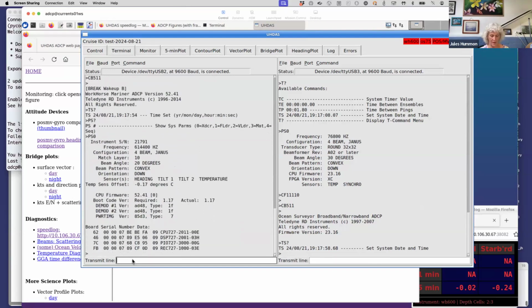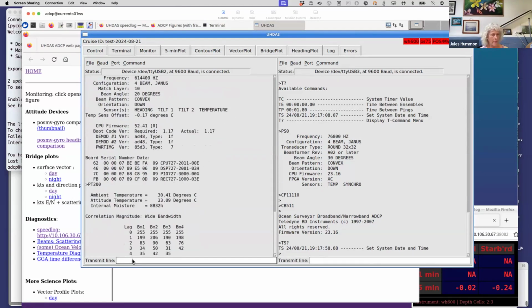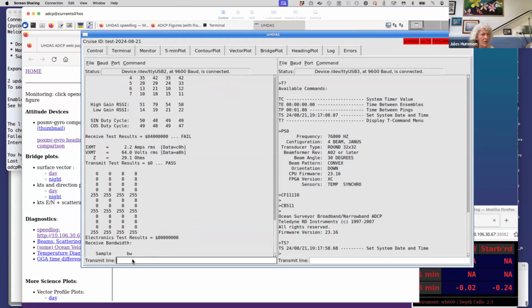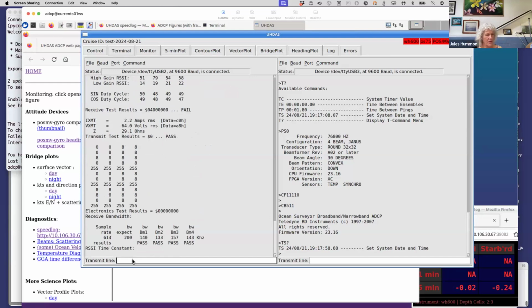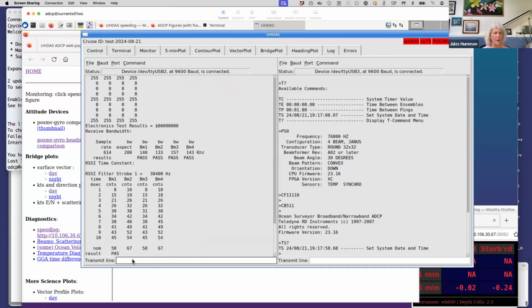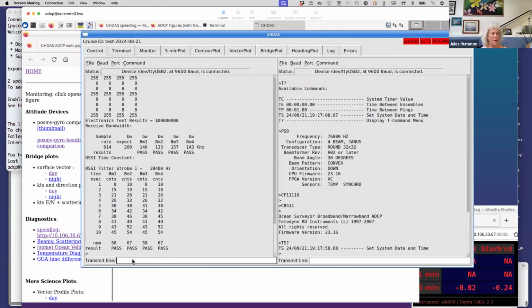Typically what they would say is, I think PT200 runs a bunch of commands that are meant to show you the health of the instrument. And I would have to say that this is not anywhere near as good as a Kongsberg multi-beam BIST test. It's just not. It's not that it lies. It's just that it's not as useful as would be nice.